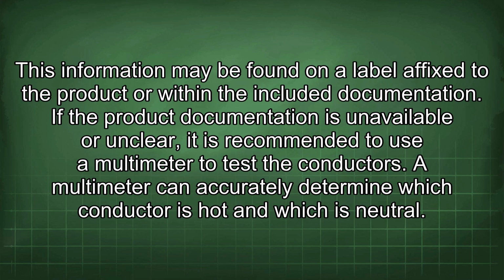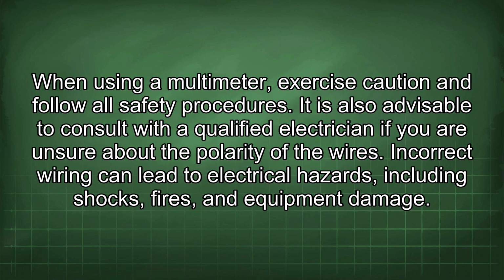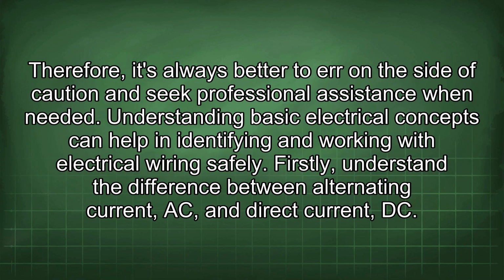If the product documentation is unavailable or unclear, it is recommended to use a multimeter to test the conductors. A multimeter can accurately determine which conductor is hot and which is neutral. When using a multimeter, exercise caution and follow all safety procedures. It is also advisable to consult with a qualified electrician if you are unsure about the polarity of the wires. Incorrect wiring can lead to electrical hazards including shocks, fires, and equipment damage. Therefore, it's always better to err on the side of caution and seek professional assistance when needed.